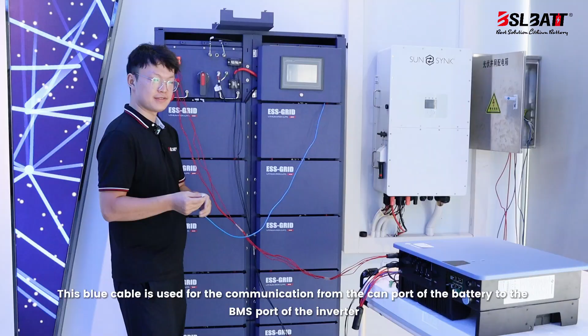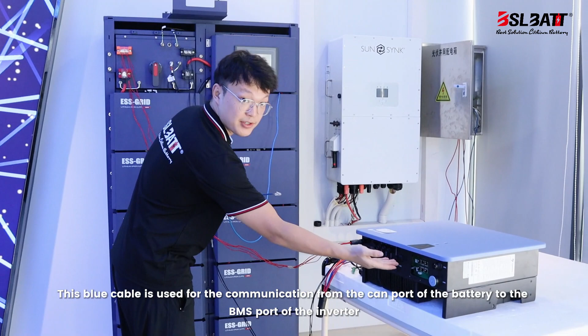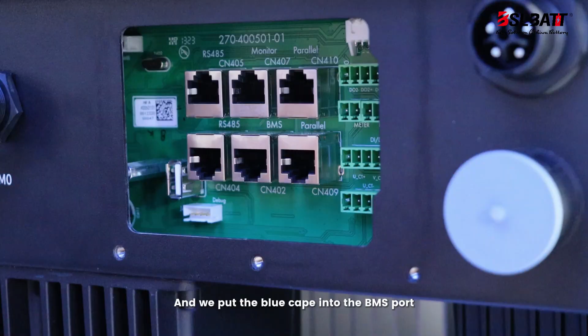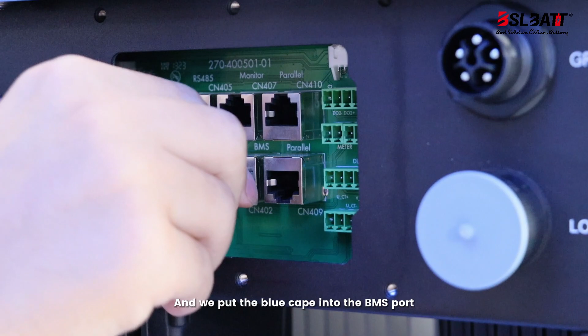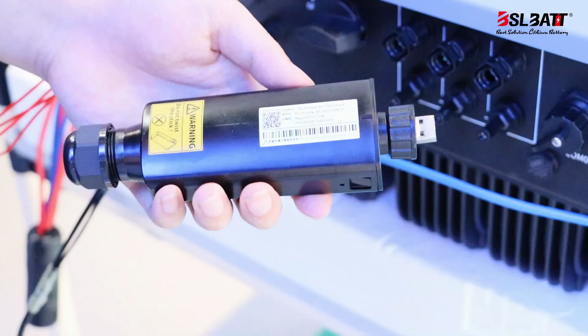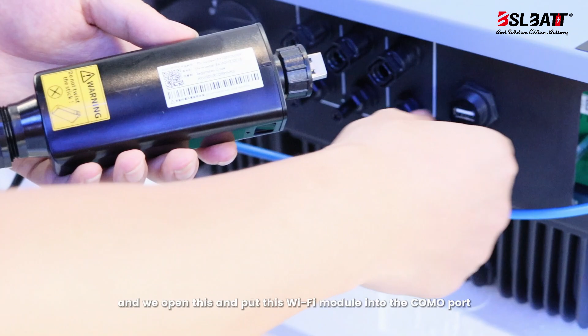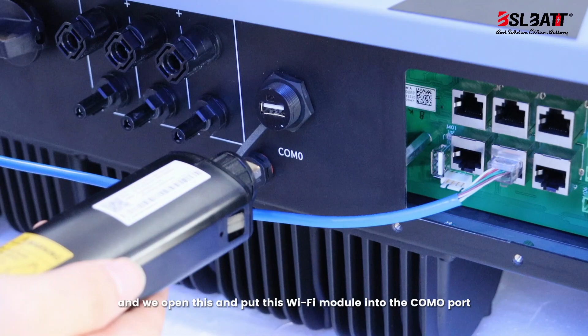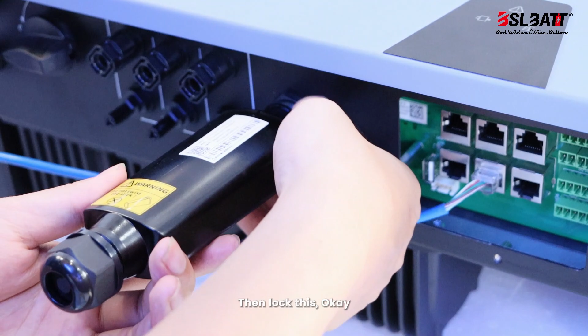This blue cable is used for the communication from the CAN port of the battery to the BMS port of the inverter, and we put the blue cable into the BMS port. That's okay. This is the Wi-Fi module of the inverter. We open this and put the Wi-Fi module into the COM0 port.